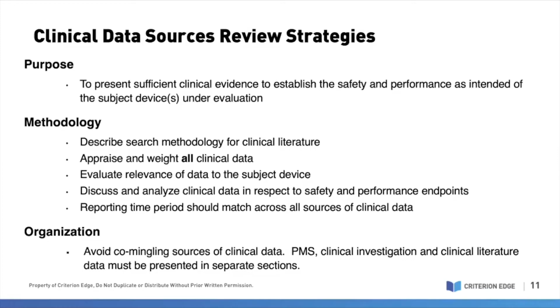Ideally, data cut time ranges should be consistent across all data sources used in the CER. Each source of the clinical data must be presented in its own section. Do not commingle the presentation and analysis of different types or sources of clinical data. Finally, because each data set presented in the CER must be analyzed against the SPRs and acceptance criteria, this means you cannot simply cut and paste analysis and conclusion statements that may have been taken from another internal document, such as the current PMS report or a CSR. Those analyses are not relevant to the analysis required in the CER.